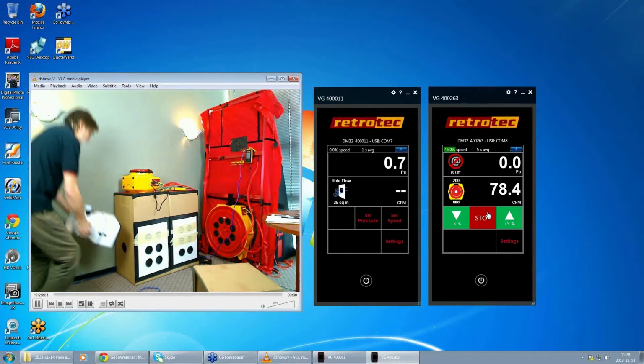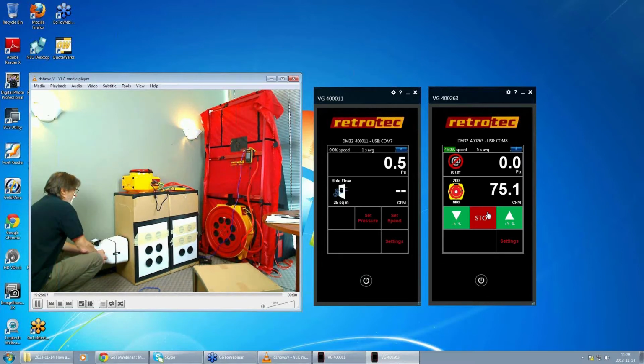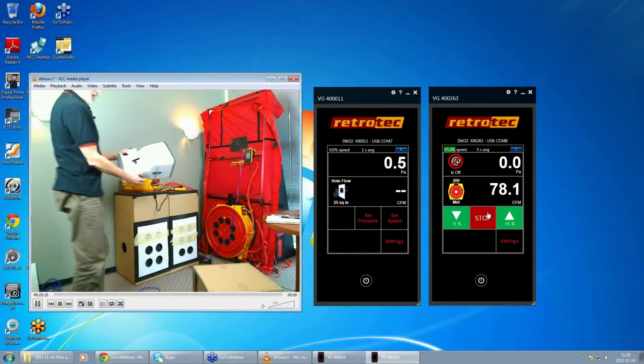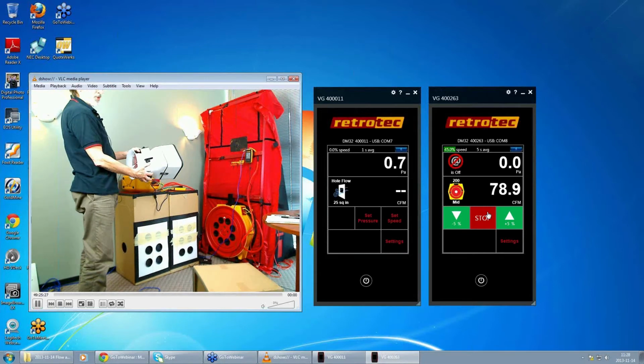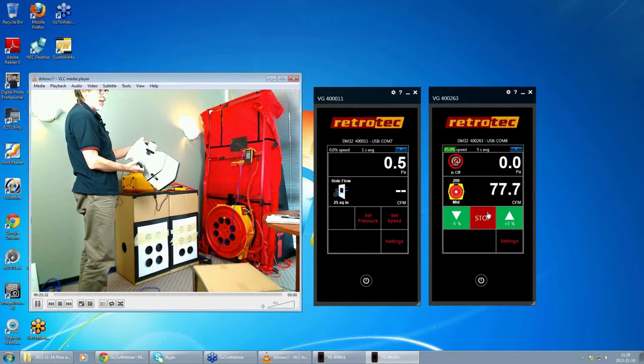Let's just try it again and see what we get the second time. So I just put the Flow Finder on here. I press the button. I hold it. It takes about 8-10 seconds. It's compensating to 0. The little fan is spinning around. .6. So it's got two readings, virtually identical. This is a very, very accurate instrument, made in Europe, expensive, but it does a fantastic job.